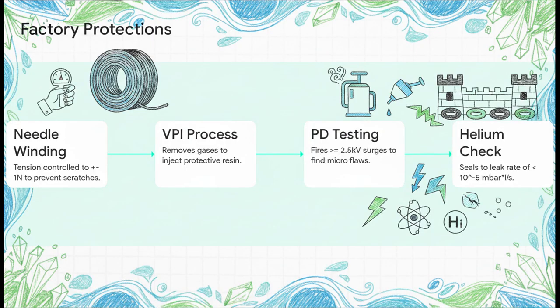The assembly line itself is hyper-controlled. Every single step matters. First up, precision needle winding keeps the wire tension controlled to within a single newton, just so the delicate insulation isn't scratched during winding. After resin injection, they run 100% online partial discharge testing, firing 2.5 kilovolt surges down the line to detect microscopic flaws as tiny as 10 picocoulombs. Finally, the entire motor is sealed with high-tech fluoroelastomer O-rings and checked with helium gas to guarantee a leak rate of less than 10 to the negative 5 millibar liters per second. It is, for all intents and purposes, an absolute fortress against water and salt.